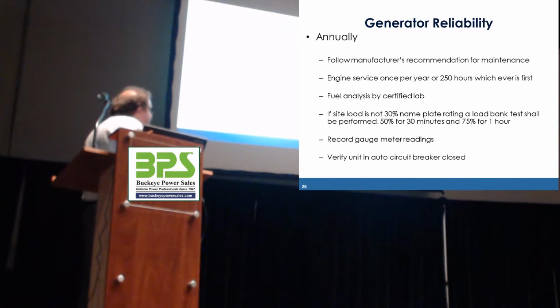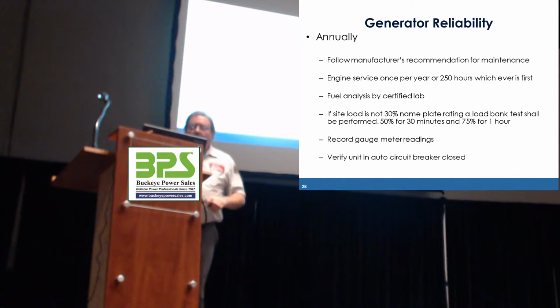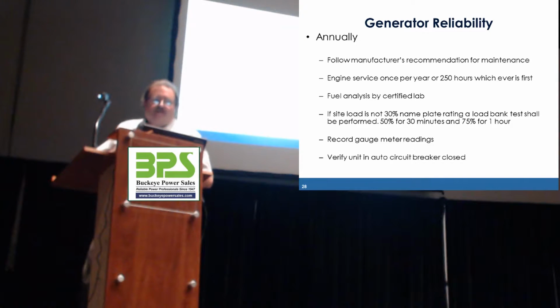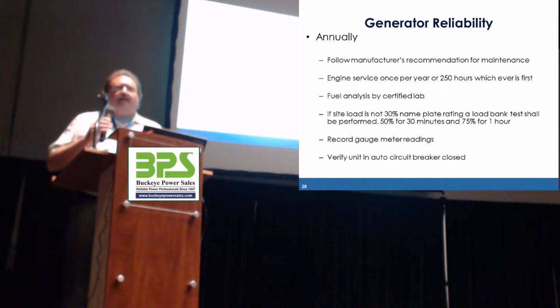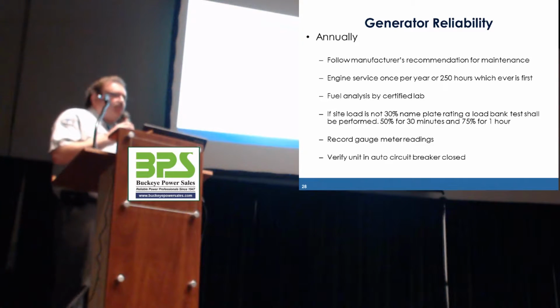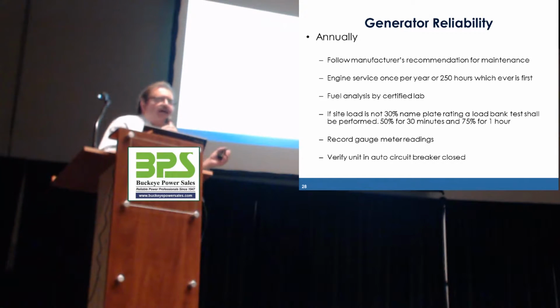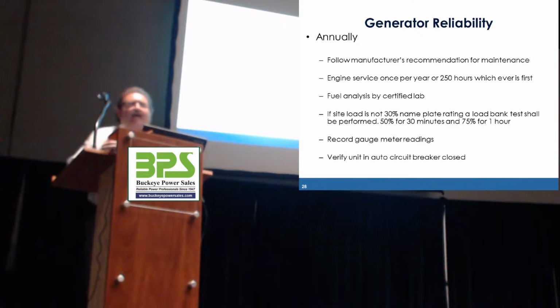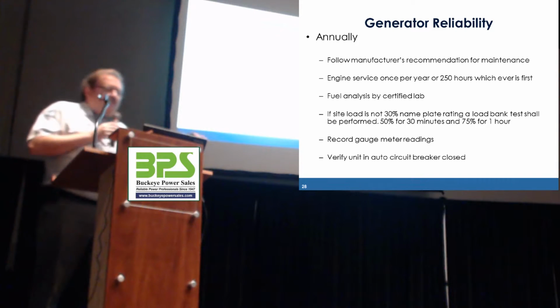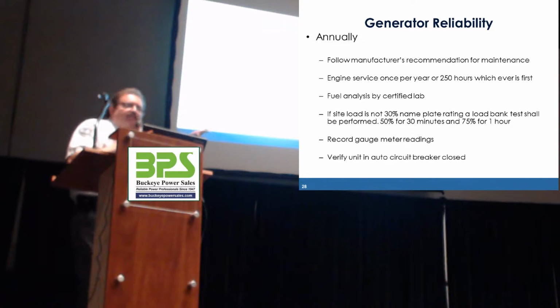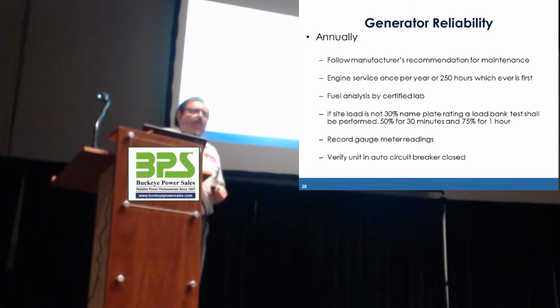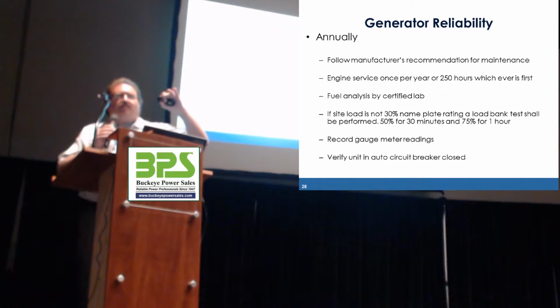If the site doesn't meet 30% nameplate rated load for diesel generators, then we have to do a load bank test, which is just what it sounds like. You bring a giant toaster out, hook it up to the generator, and you run it under load: 50% for 30 minutes, then 75% for the next hour. Okay, that's what code tells us to do.